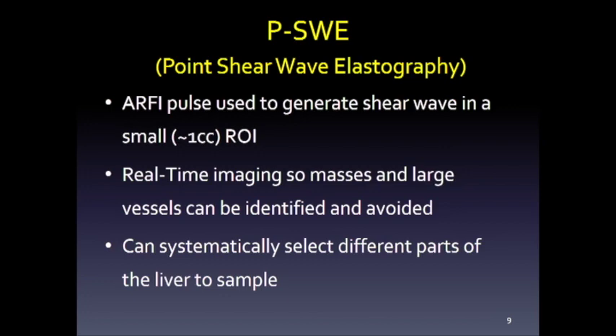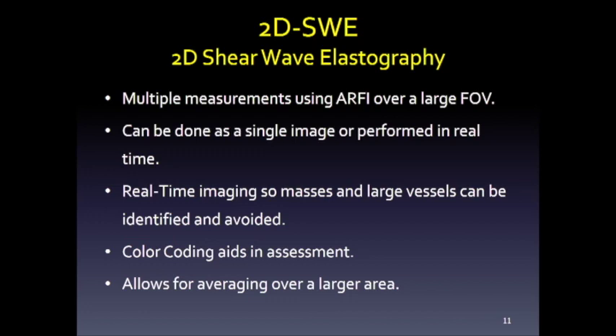For point shear wave, we use an ARFI pulse — an acoustic radiation force impulse — which is a high-energy pulse that generates shear waves. We're looking at about a 1cc area in real time, so we can identify masses and vessels and avoid those when taking measurements. 2D shear wave uses the same principle but over a much larger area, and we place an ROI within that box to get a reading.